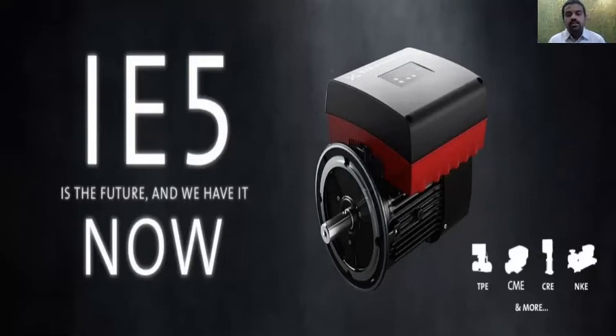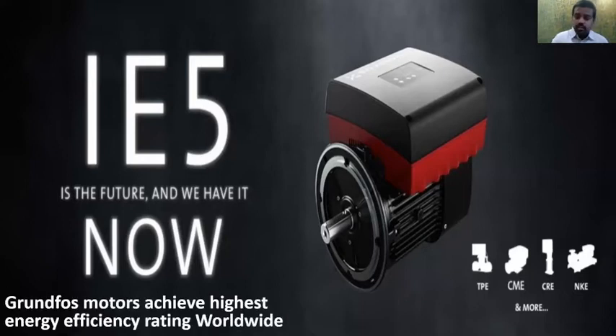So let us see what is the efficiency level that we operate with respect to motors and drives. It's something closer to 88 to 90% with IE3 and external drives connected together, which is an induction-based motor principle. And now we are with IE5 efficiency level of motor, which works based on permanent magnet motor technology with inbuilt or integrated drives, with controls and sensors, everything. What we are actually trying to improve here is efficiency by 5% at full load and 20 to 30% at part load, depending on the application and the load patterns we have. So that's something new on the product side, on the efficiency improvement.